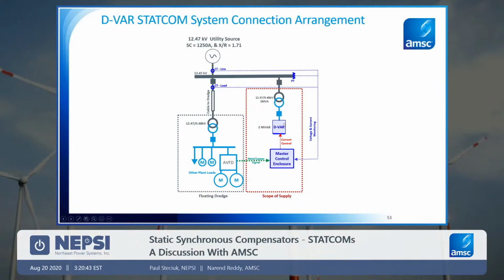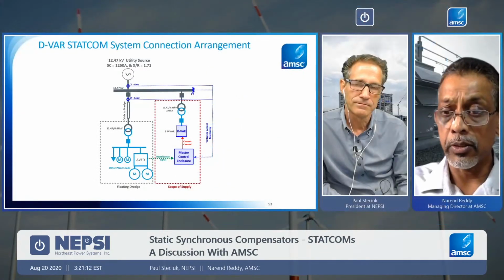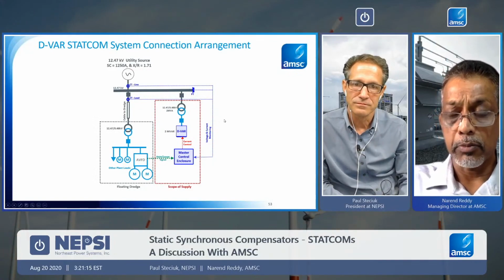Typically, AMSC's scope of supply would be the Statcom unit, the transformer, and the master controller, and we'd work with the customer on whether we install it or they have a balance of plant installer who can do that. Beyond the Statcom unit and the transformer that's supplied, it's a utility grade installation, integrated with any other equipment, in terms of protection equipment, control, or any of the standards that need to be employed. It's really the local utilities and the local requirements that would prevail for those.